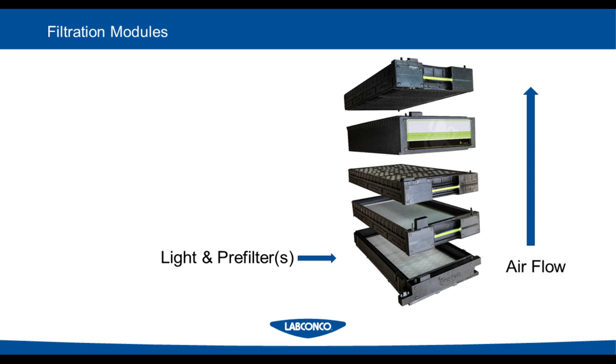And if you're not working with any hazardous particulates or solids that may become particulates or high temperature acid use, then you would not need the HEPA filter. And I'll talk about how we determine when and where. On top of that would be the first carbon filter. So this is the one I like to describe as doing all the heavy lifting. This is doing the chemical adsorption day in and day out, capturing everything generated within that hood and stopping it at that point. Coming off the outlet side of this filter will be very clean air.